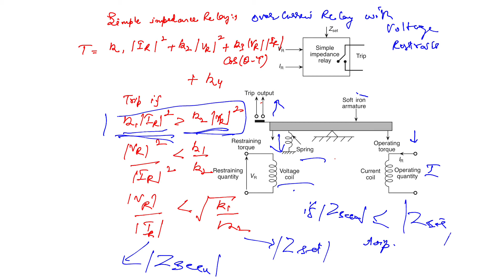Now the relay will trip if this condition is followed, that is K1 IR square is greater than K2 VR square. Similarly, as we have done in the previous case, the Z seen is less than the Z set. So the balanced beam structure implements the simple impedance relay. So this is how the simple impedance relay can be represented by the balanced beam structure.